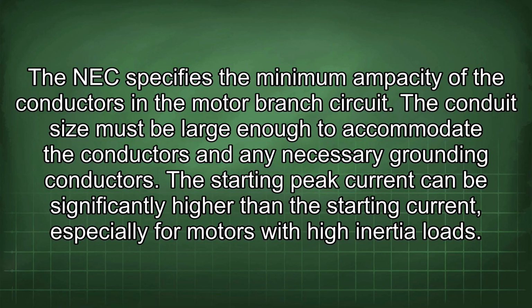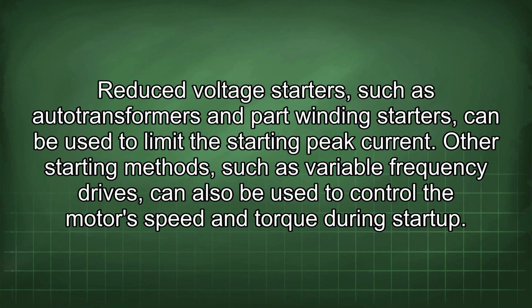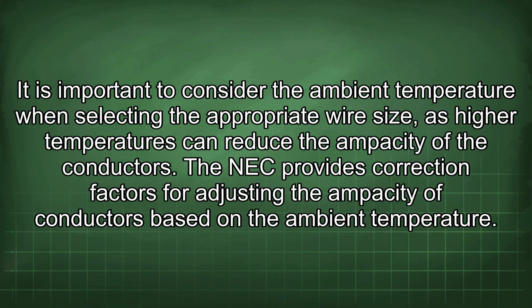The starting peak current can be significantly higher than the starting current, especially for motors with high inertia loads. Reduced voltage starters, such as auto-transformers and part-winding starters, can be used to limit the starting peak current. Other starting methods, such as variable frequency drives, can also be used to control the motor's speed and torque during startup. It is important to consider the ambient temperature when selecting the appropriate wire size, as higher temperatures can reduce the ampacity of the conductors.